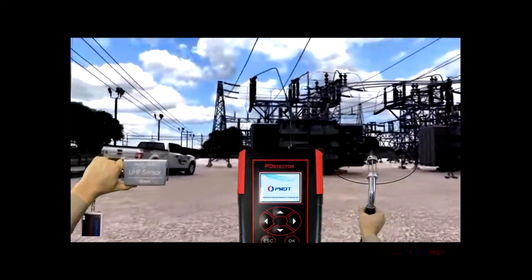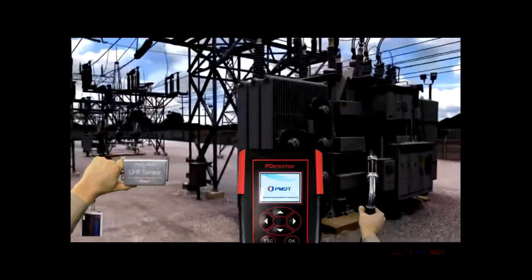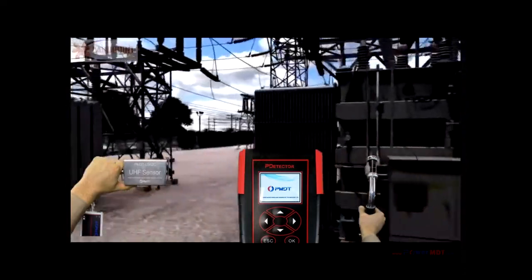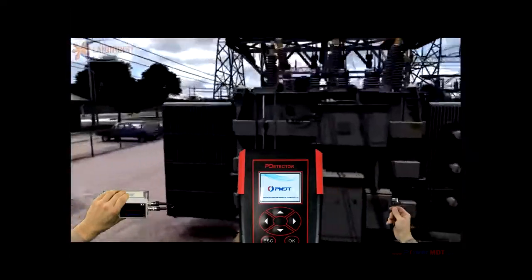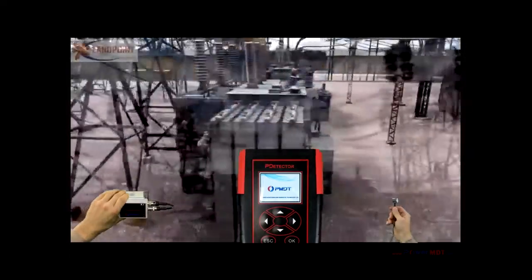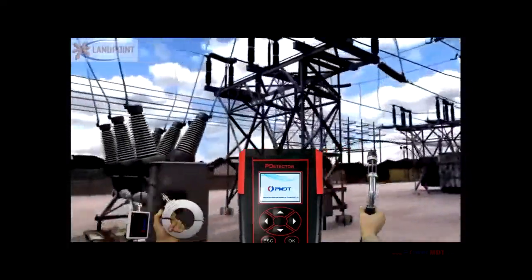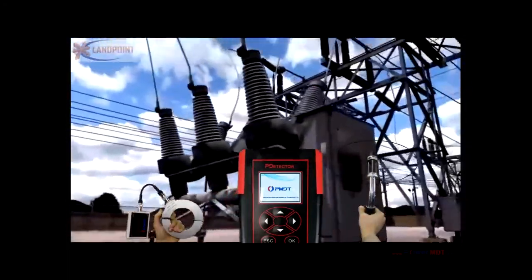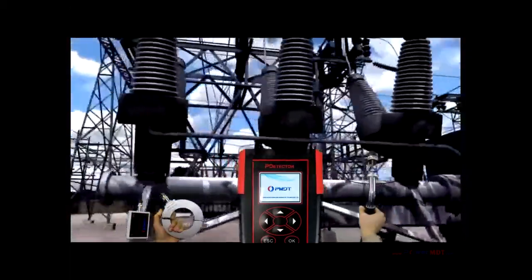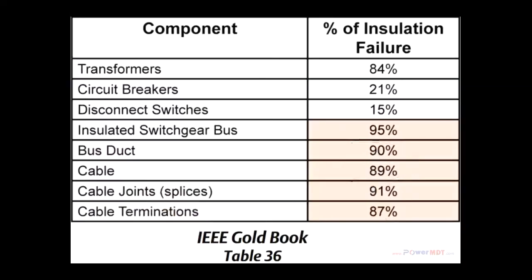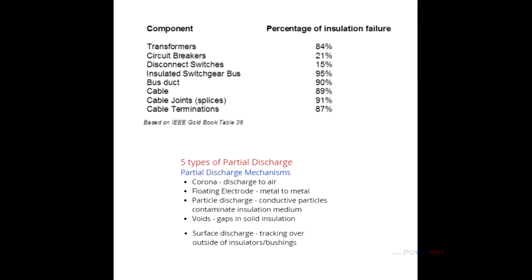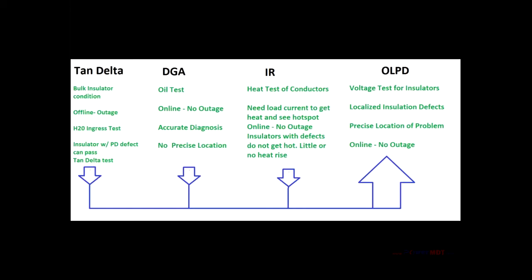Online PD testing is a pre-outage insulation inspection which is performed on live, energized, medium or high-voltage power equipment without a service interruption or outage. According to the IEEE Gold Book, insulation failure is the cause of 80% of power equipment failures. Online PD testing provides valuable information about insulation condition even when there is no opportunity for an outage to perform conventional tests.